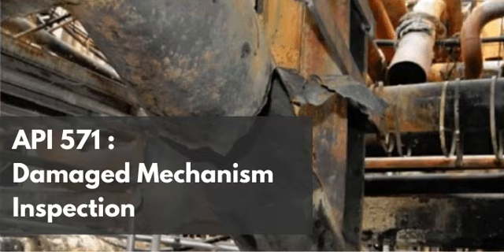So you are plastically deforming the metal in place just to create a friction seal. You are cold working it to its absolute mechanical limit. The metal is permanently crushed and stretched. This rolling process leaves behind an area of extreme, localized residual tensile stress exactly at the transition point where the tube exits the tube sheet.